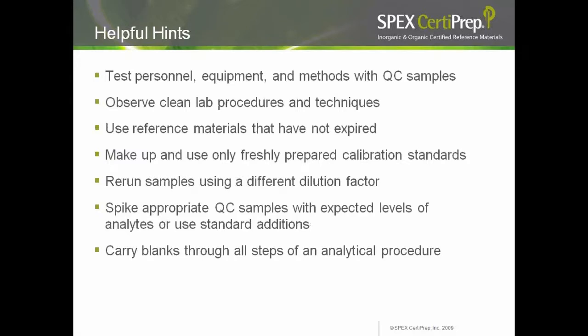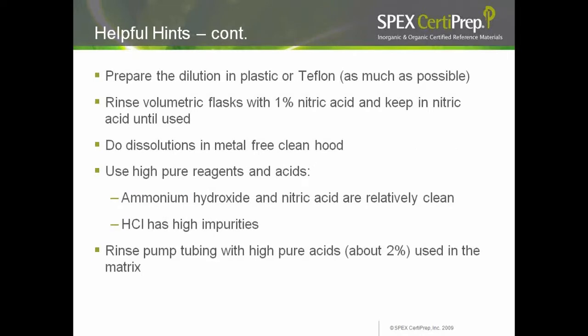Use reference materials that have not expired. Make up and use only freshly prepared calibration standards. Rerun samples using a different dilution factor to check your original analysis. Spike appropriate QC samples with expected levels of analytes or use standard additions. Carry blanks through all steps of an analytical procedure. Prepare dilutions in plastic or Teflon as much as possible. Rinse volumetric flasks with 1% nitric acid and keep in nitric acid until used. Follow your lab protocol — in the absence of one, you can use these guidelines. Do dilutions in a metal-free clean hood and use high-pure reagents and acids.